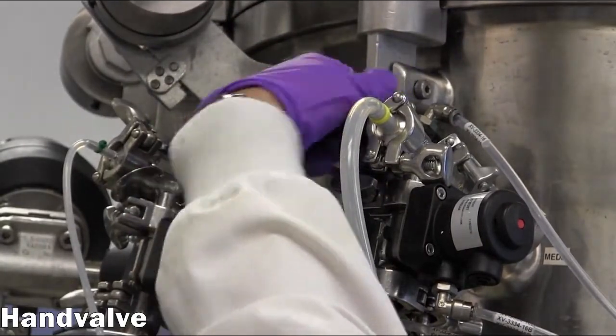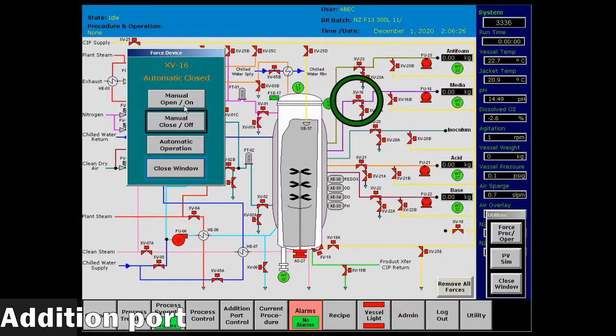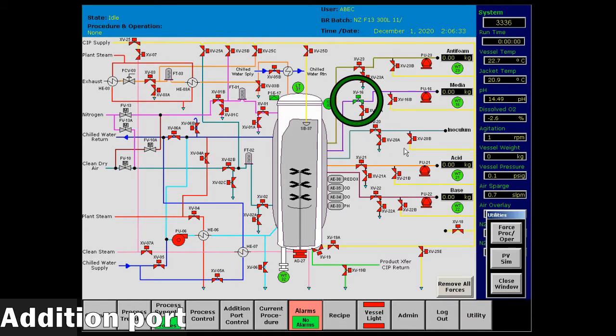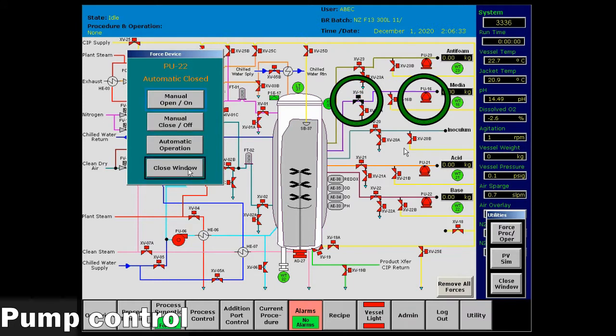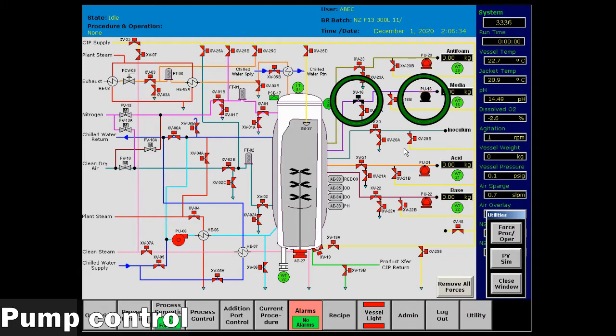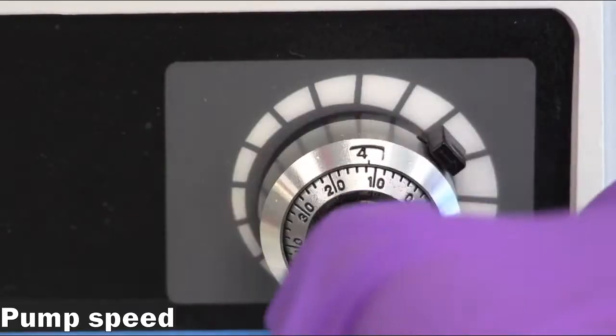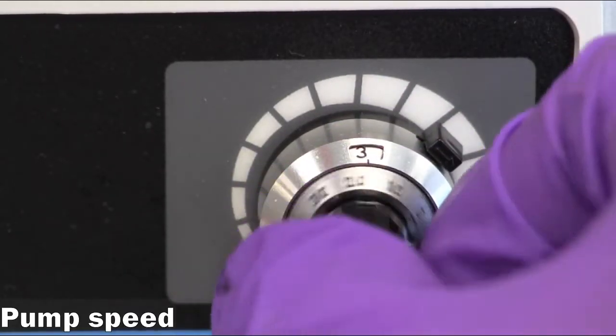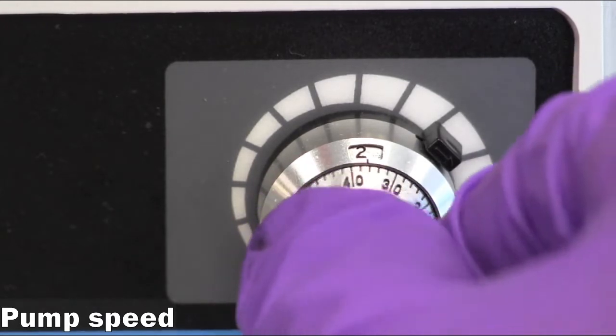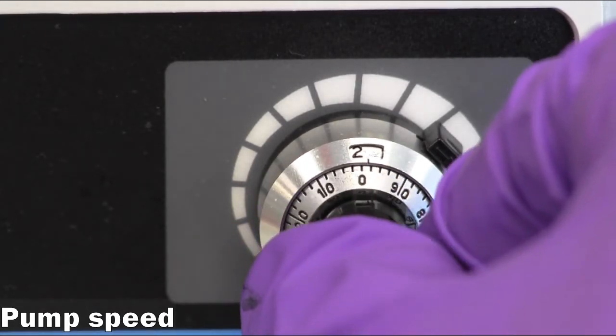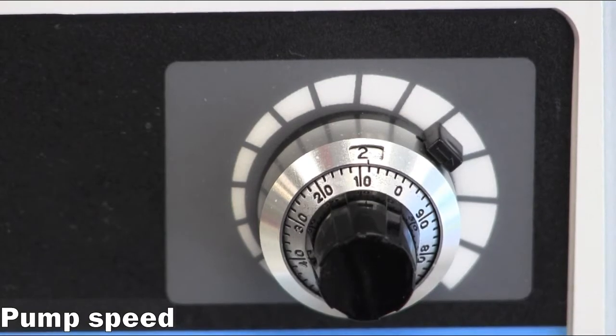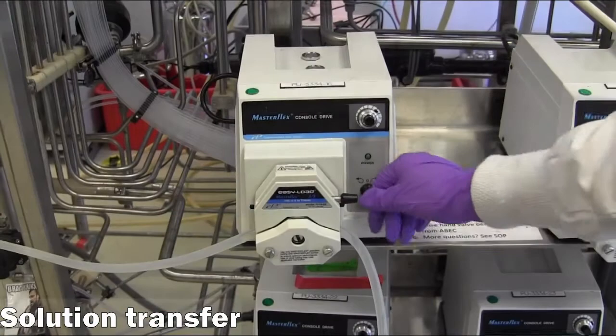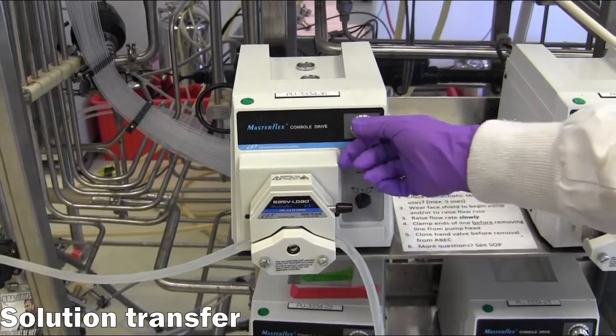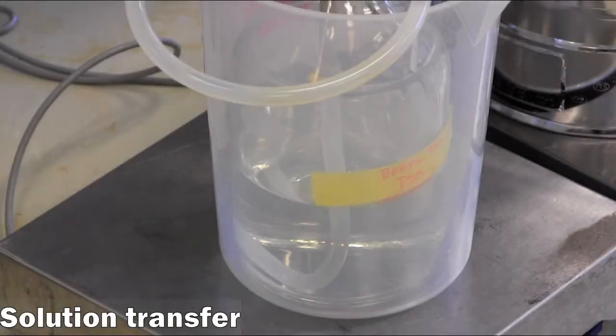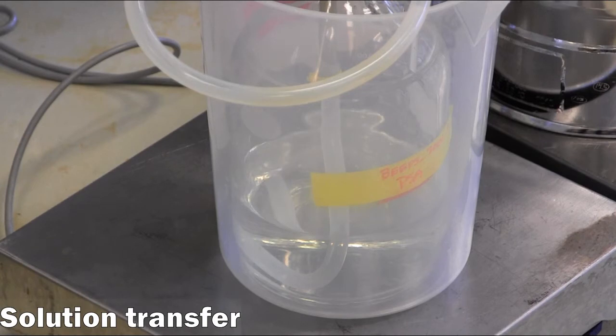Open the hand valve on the assembly, then open the corresponding port on the HMI. Next, enable local pump control by turning on the pump. Use the dial on the pump to adjust the speed to a safe operating set point. It's recommended to start the pump at 2.1 and slowly increase the speed once the transfer has started. Flip the switch to the left to start pumping. The solution is now being transferred into the reactor through a sterile connection.